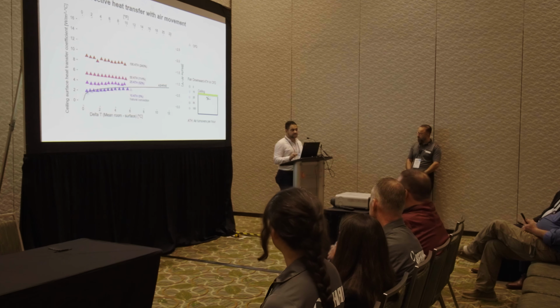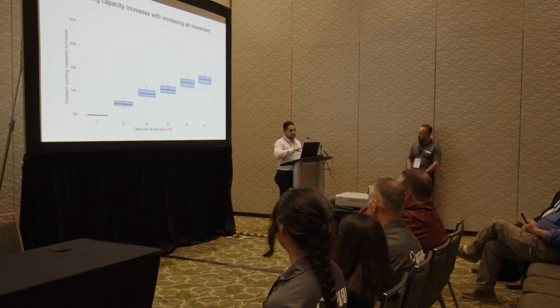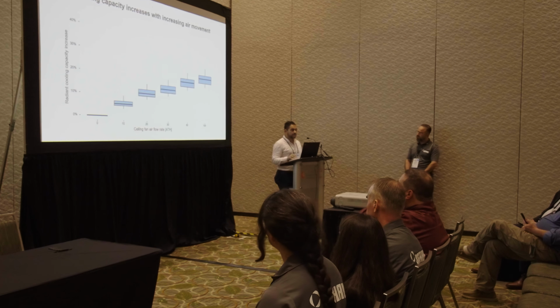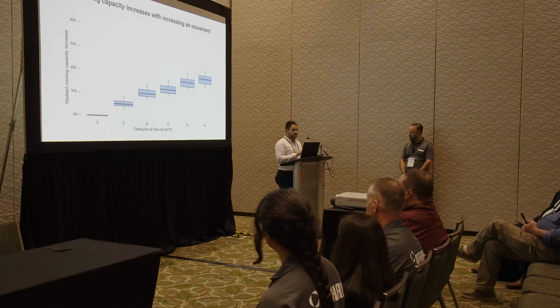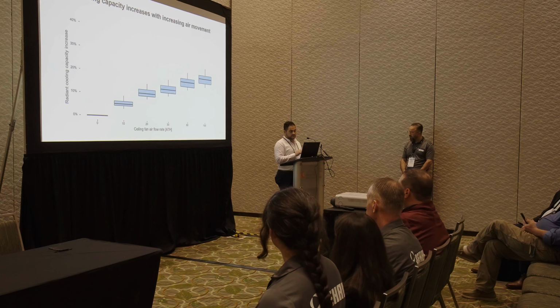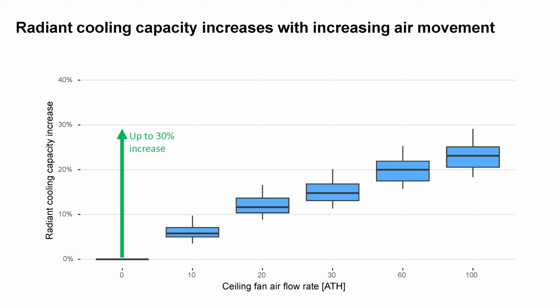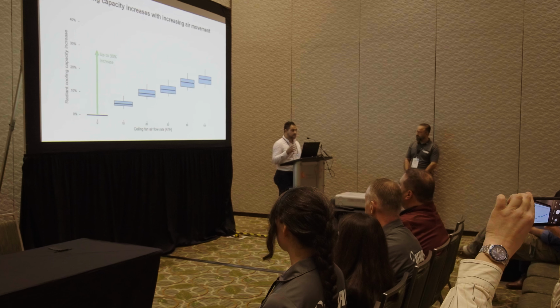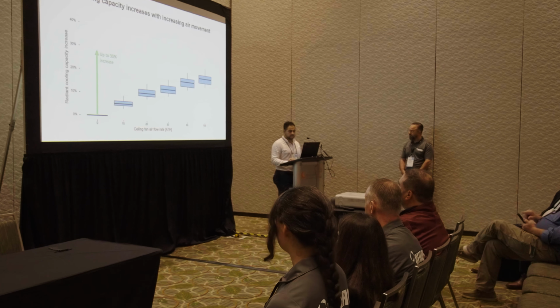This is just the surface heat transfer coefficients, and that's why we go into the second phase of the study, where we input the heat transfer coefficients that we found through CFD into EnergyPlus, to see the effect of using a ceiling fan for various design parameters. As you can see here, the total radiant cooling capacity of the system increases by up to about 30% as we go to the maximum speed setting of the fan.